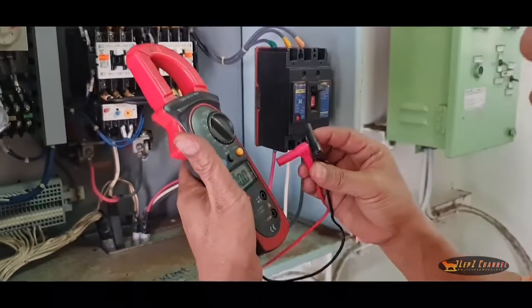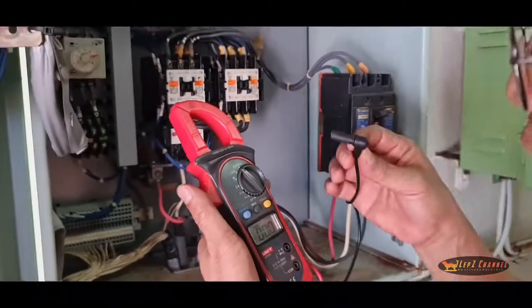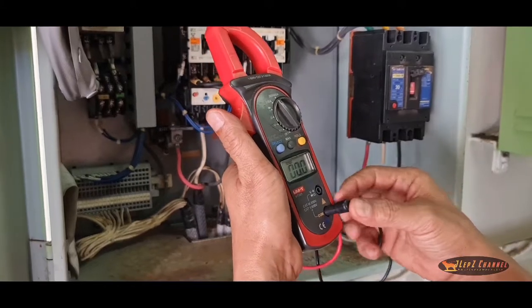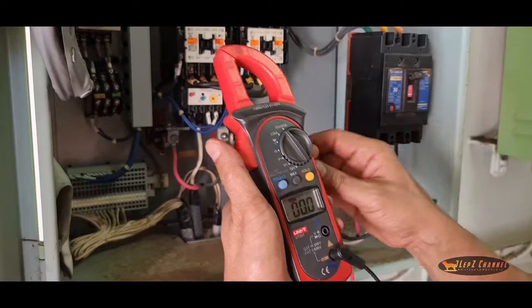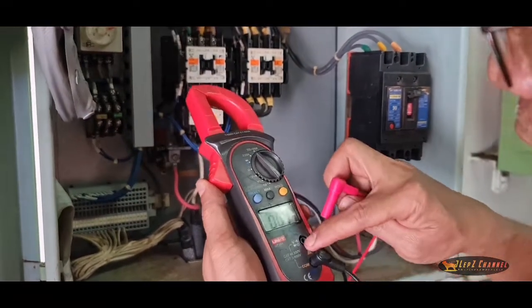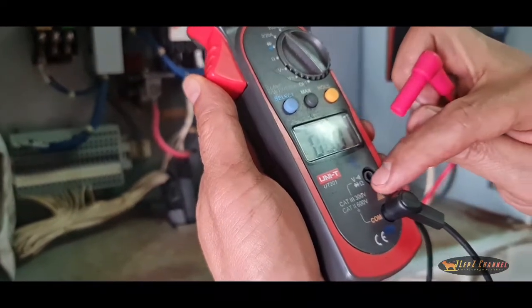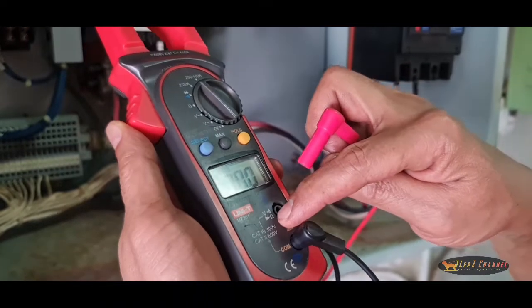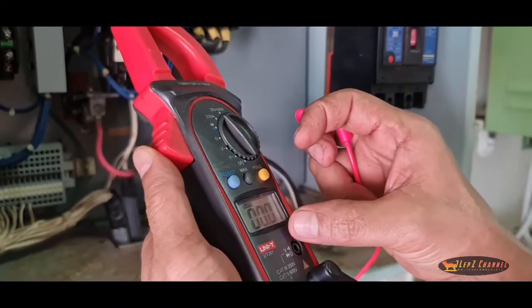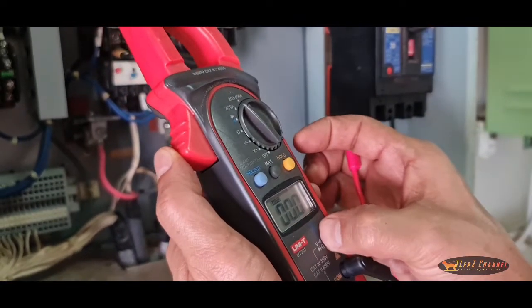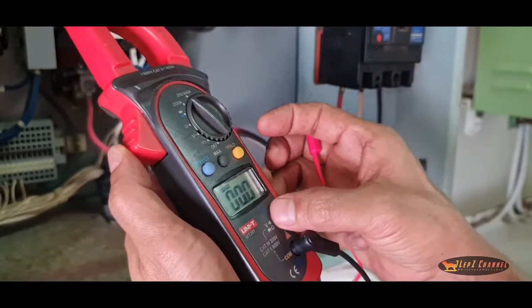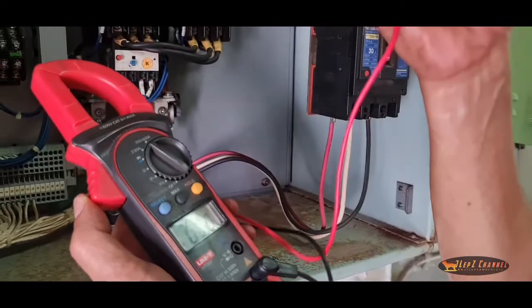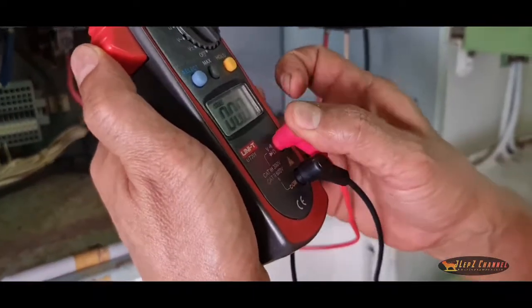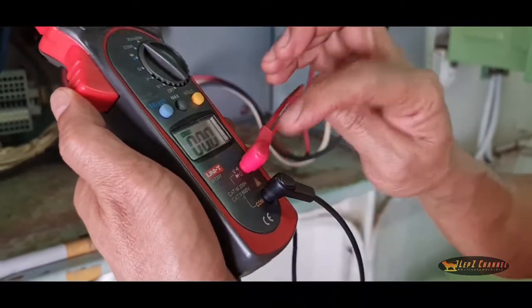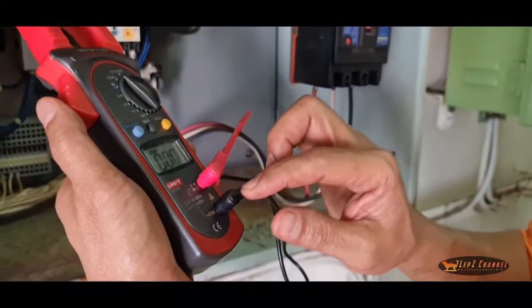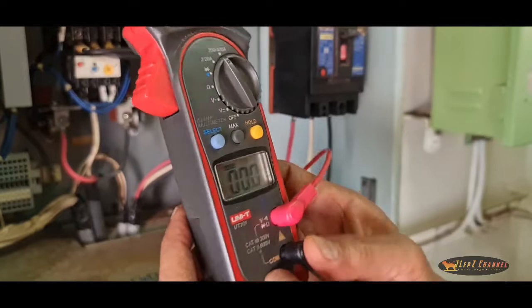Always take note that the black plug shall be plugged into common, because there are three or four parameters that you are going to test. One is the continuity test or the resistance test, and the diode test, and this one, the smaller one, is the continuity test, the smallest resistance, and the other one is the voltage test. This red one is always here. Even if you test the diode, you always put the red here. The black is always on the common side.